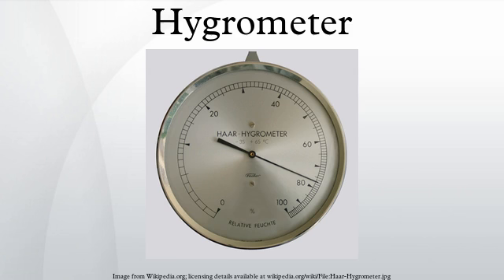A hygrometer is an instrument used for measuring the moisture content in the atmosphere. Humidity measurement instruments usually rely on measurements of some other quantity such as temperature, pressure, mass, or a mechanical or electrical change in a substance as moisture is absorbed. By calibration and calculation, these measured quantities can lead to a measurement of humidity. Modern electronic devices use temperature of condensation, or changes in electrical capacitance or resistance to measure humidity differences.